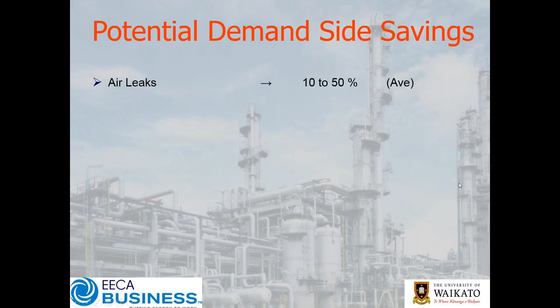Number one, top of the rank, is always going to be air leaks — potentially 10 to 50% reductions. There are not too many sites where it's less than 10%. If you are on a site which has a very good leak rate — very, very small — you will know about it; you'll see it in the housekeeping. When we do this training, generally what you'll find is within the first five minutes in the plant room, there are things that will point clearly to whether you could be looking at a best-in-class system. Very rare, very few and far between, but they do exist.